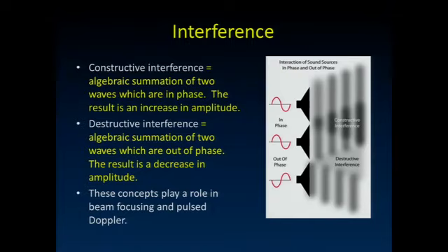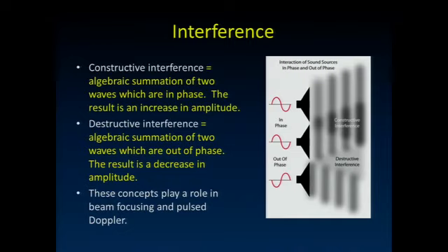Ultrasound waves can interfere with each other. Destructive interference causes cancellation. Constructive interference is used to our advantage in small phased array transducers — by stimulating different elements at specific timings, we create multiple ultrasound waves that constructively interfere to steer the beam in the desired direction.